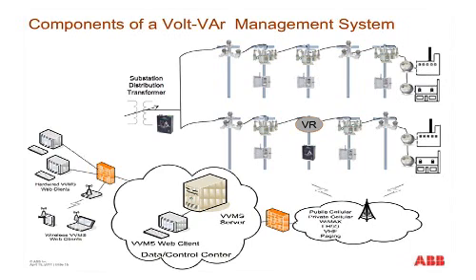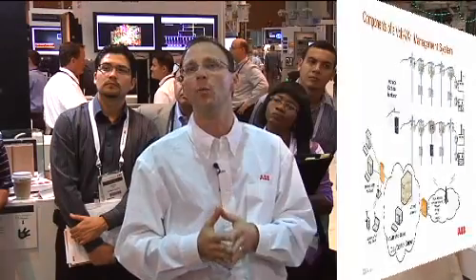We install a network of some form. Often utilities already have it, but some kind of either one-way or two-way communications. The newer communications are WiMAX or frequency hopping spread spectrum technology, but even the older technology of VHF or paging, if you have it existing, is a usable technology for one-way. Public cellular is gaining momentum as well, and that's another opportunity.